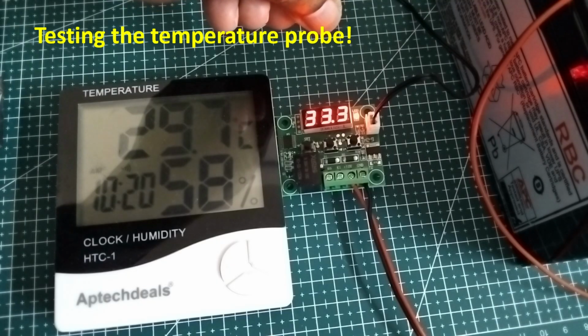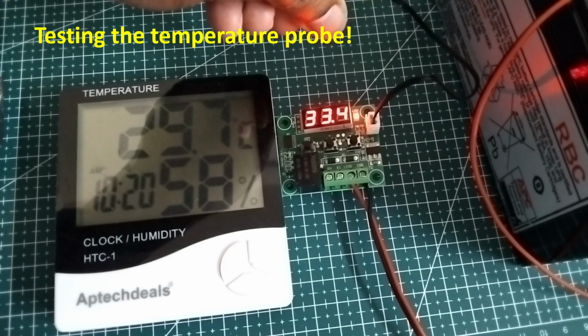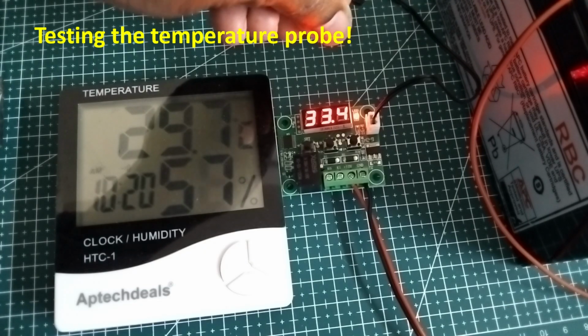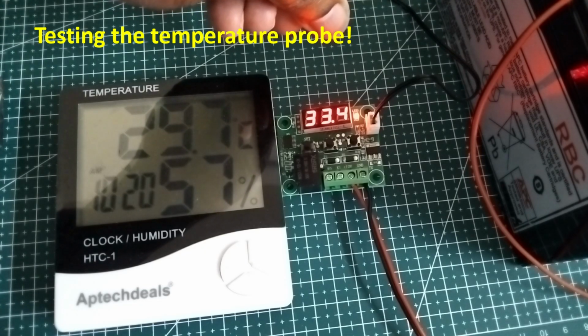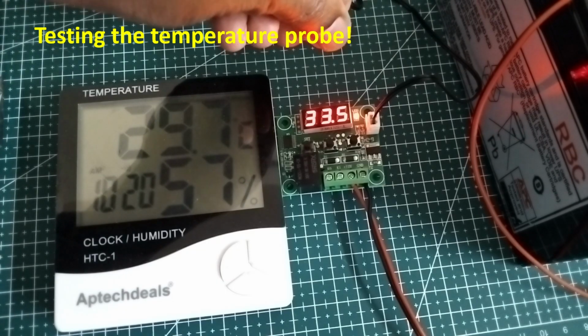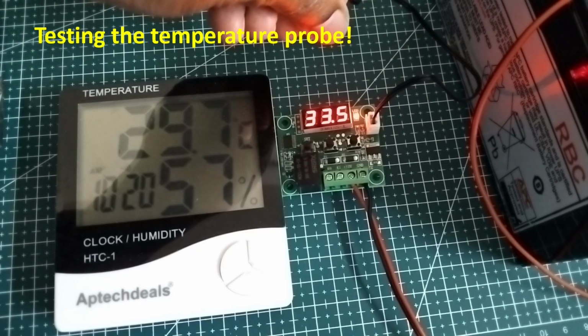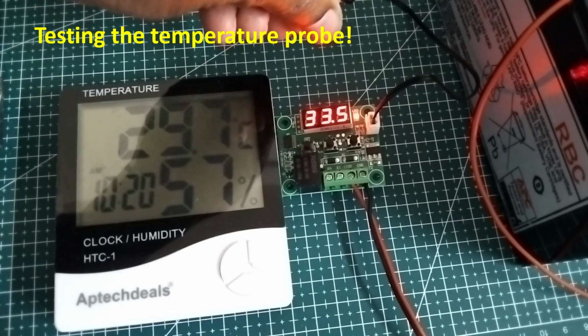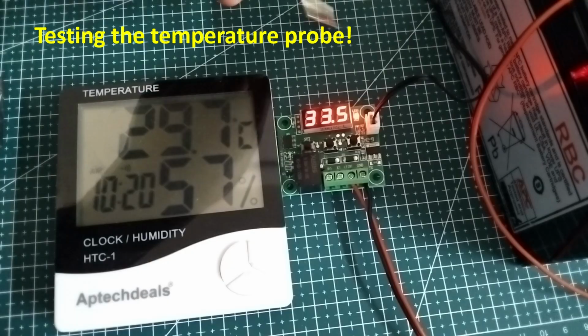I thought of putting it in hot water to test it, but then I thought of a simpler way - just holding it will make the temperature rise, so this should be working properly. It's about 33.4, not exactly body temperature, which should be 37 degrees centigrade, but it's gradually going up. I'm stopping this test here.